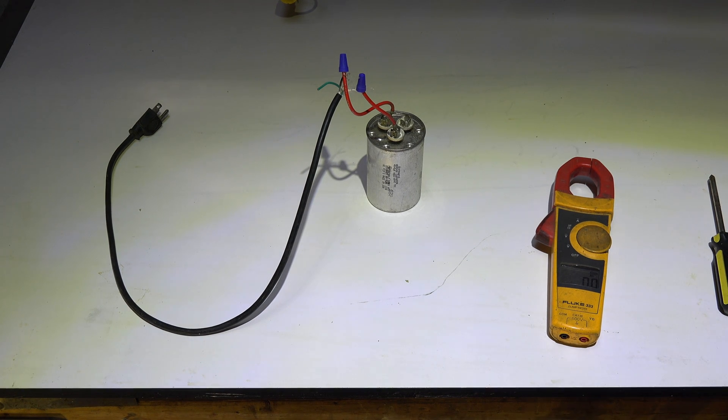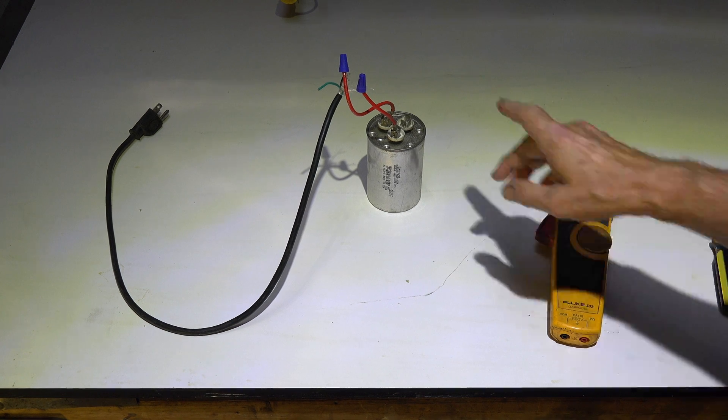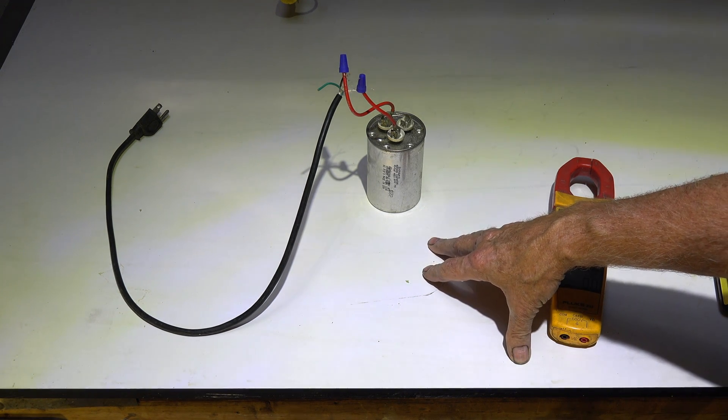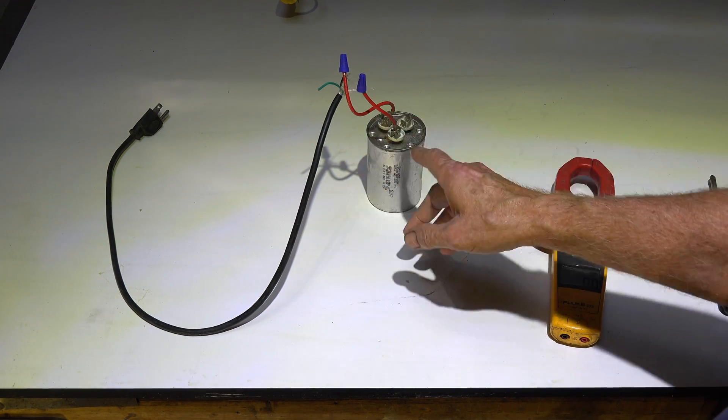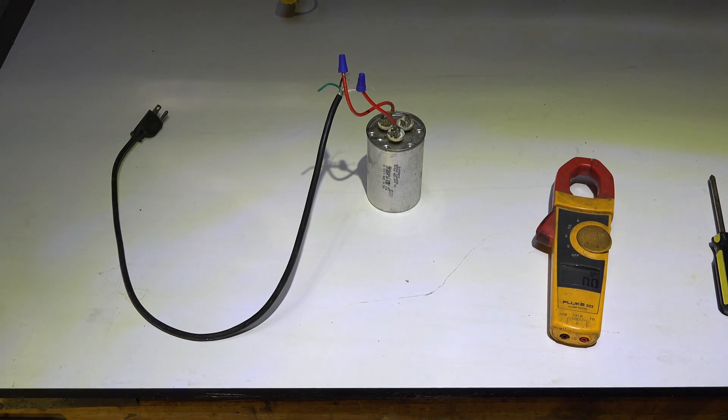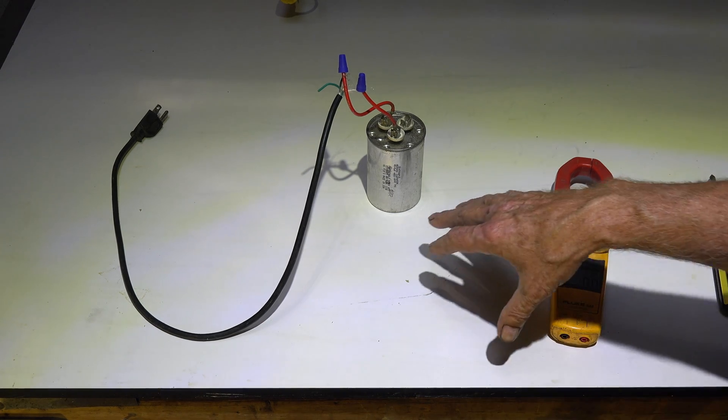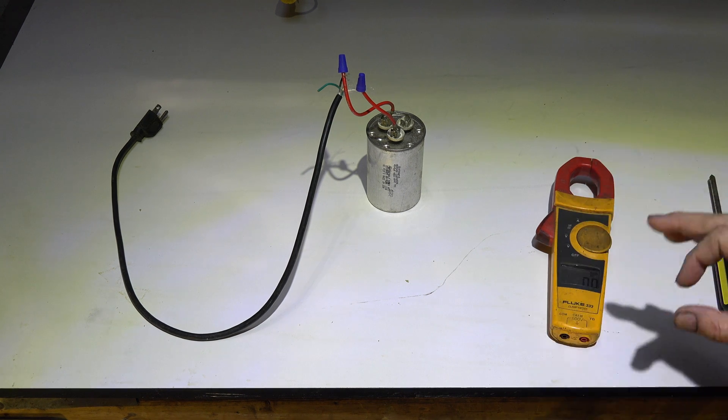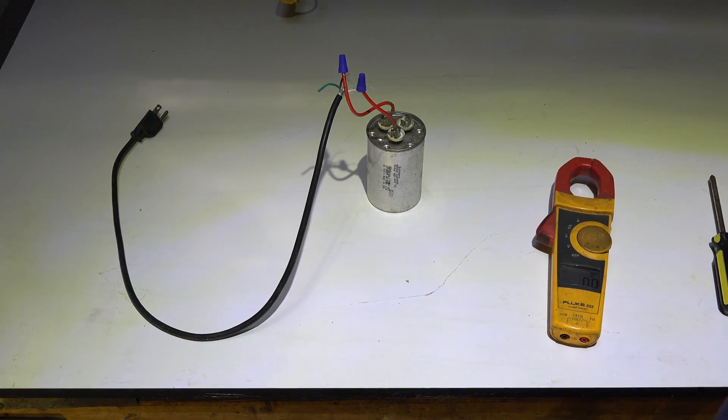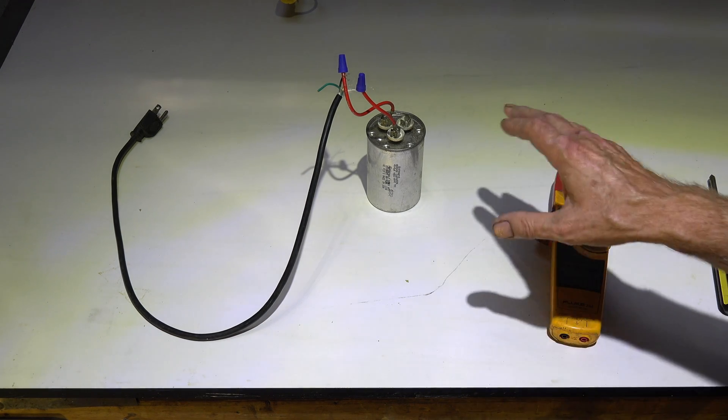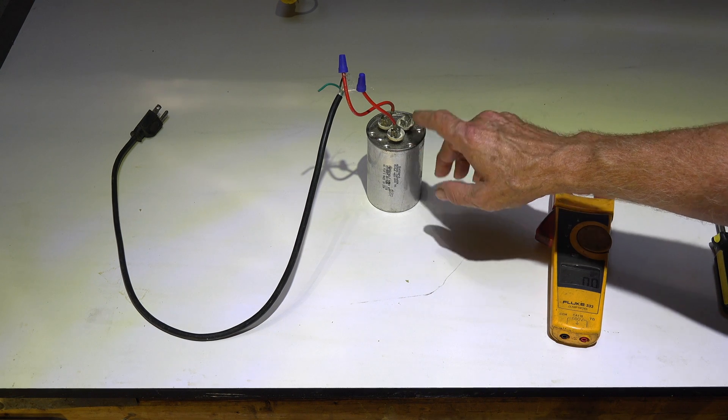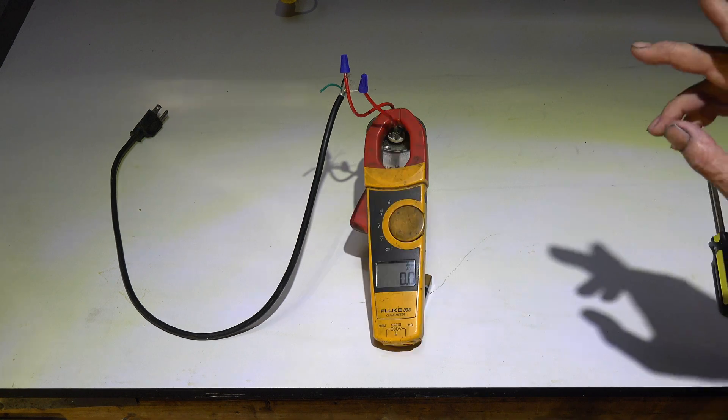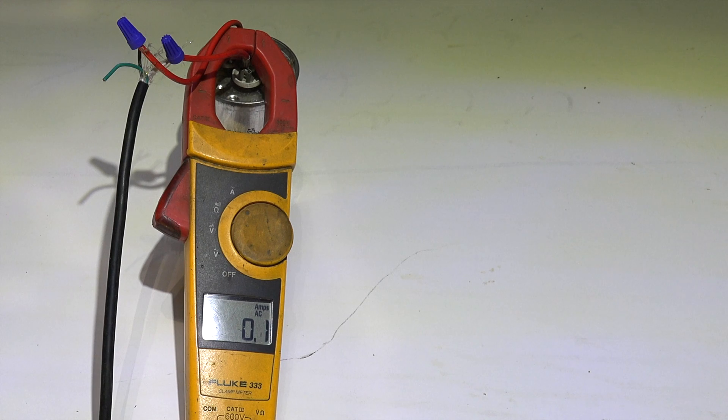Now I've set up a circuit to test what kind of amperage will run through one of these capacitors when power is applied to it. I've just got a little cord here. I'm going to plug the cord in. It's essentially the same circuit that's in that compressor. The power actually goes through the windings of the compressor, but the windings of the compressor have very little resistance. So there won't be much of a load on it. It is the capacitor that is providing this current regulation. When I plug this in, we're going to get an amp draw.